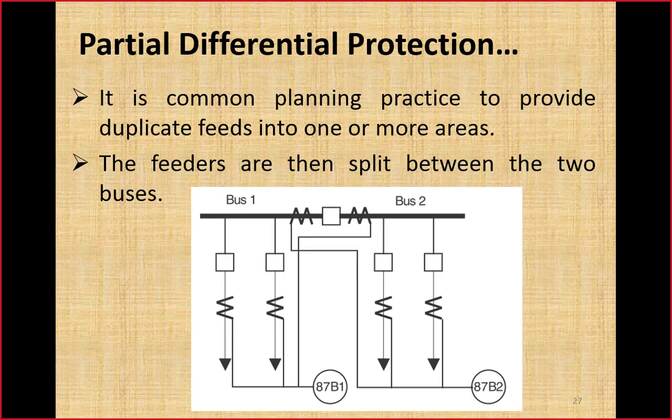So in order to increase the reliability, we split the bus into 2. The same single bus now has 2 portions. That becomes a split bus configuration. A tiebreaker is used to connect the buses together to make them work as a single bus, and when this breaker is open, they are separate buses.